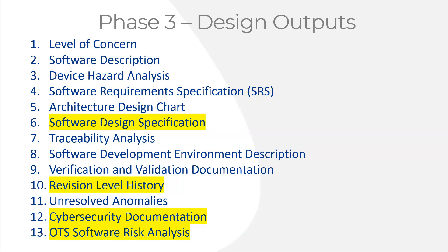Before reaching that iterative development, you need to identify design specifications for your software, maintain a revision level updated every time you make a change, and go through the cybersecurity documentation to document what risk controls you'll put in place. Any off-the-shelf libraries or operating systems you use require a documented risk analysis. So in this phase, you're not only documenting design specs but also conducting and documenting risk analysis and risk evaluation. Each time you compile and verify or validate — whether unit test or integration test — if you fail, you go back to your design outputs and update them.